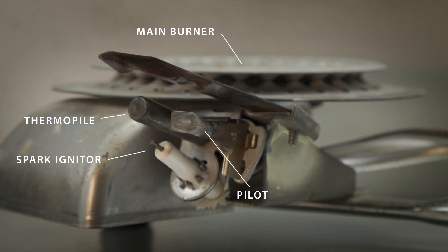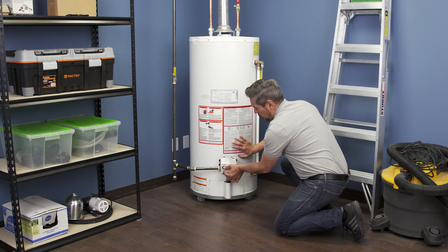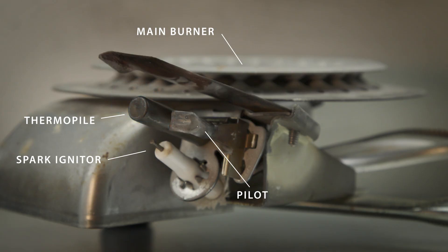Now if the thermopile is faulty, then it will also prevent the pilot from staying lit. If you try to light the pilot and it won't stay lit, then it could be a problem with the thermopile or thermal cutoff switch.